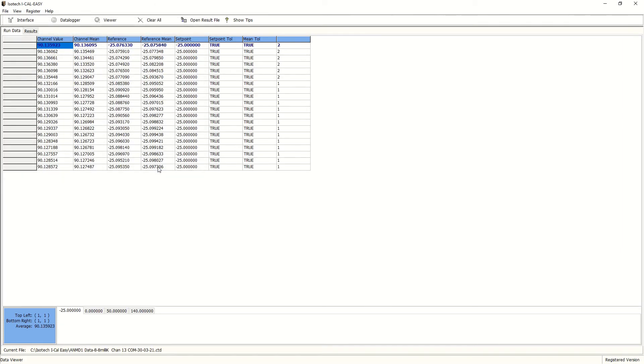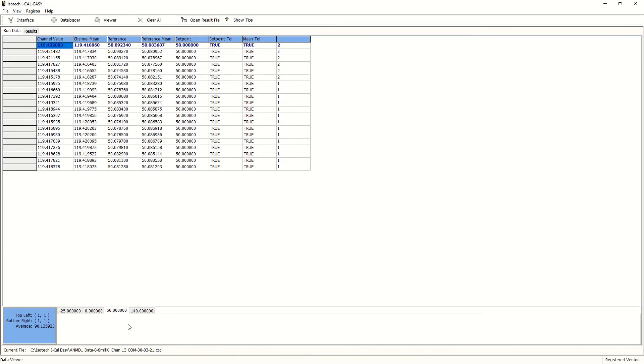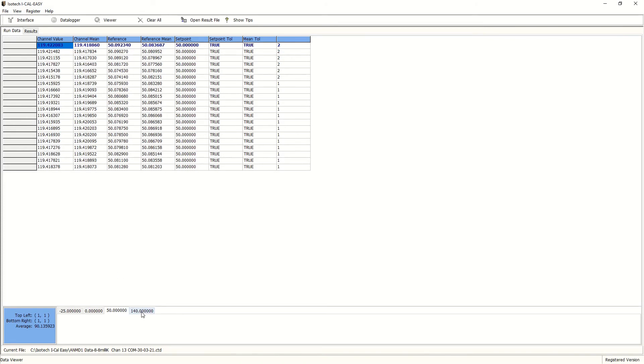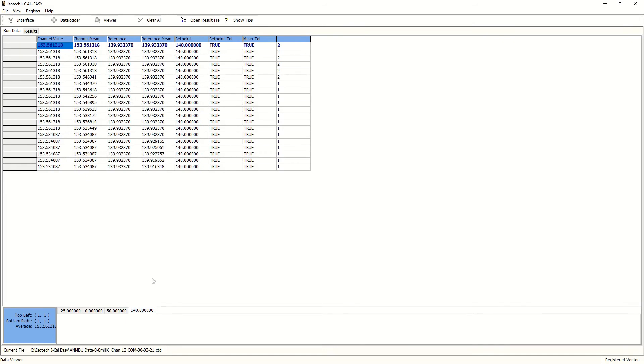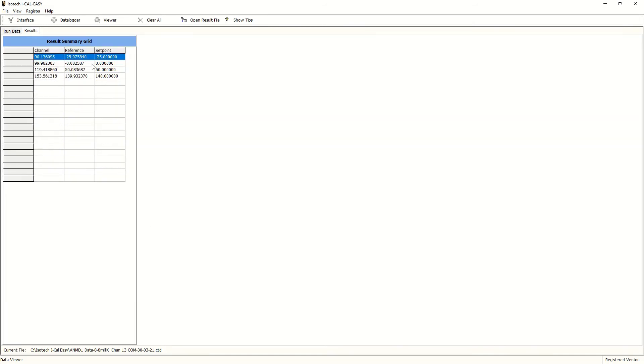This brings in all the values for each of the temperature points. We can see it passed its test for stability because all of these readings are true and then it took a reading at each of the temperature points that we programmed in and produces a shortened version of the results.